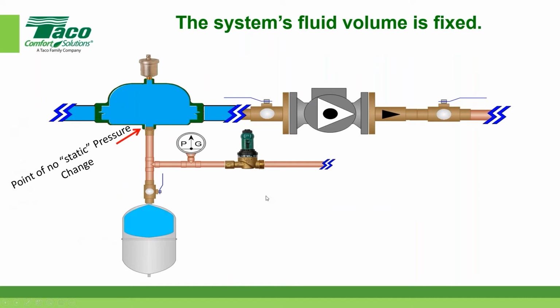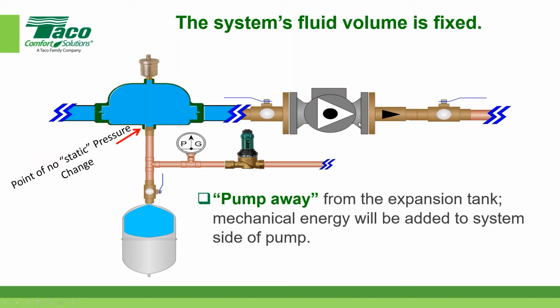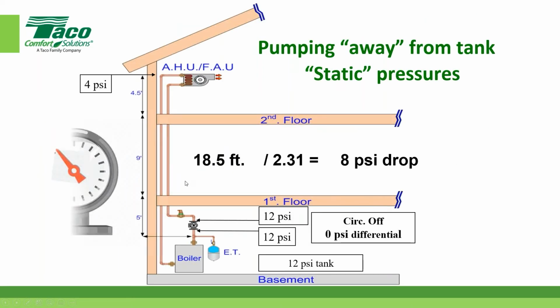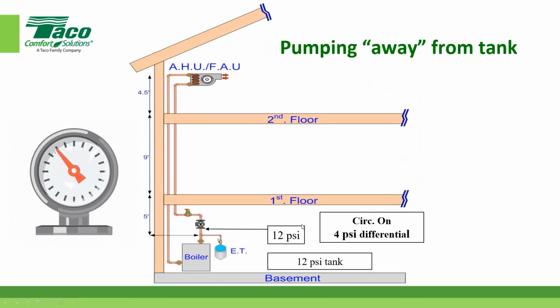And I've got to show you how to do it right as well, right? So here's a circulator that's pumping away from the point of no static pressure change here. That way, everything the circ can add will go out to the system, like I'll show you here. Okay. Let's say that now the circulator's here. I'm pumping away from the point of no pressure change. Remember, on the last slide, it was over here pumping into it. Now it's pumping away from it. Let's go ahead and see what happens when I add that 4 PSI.